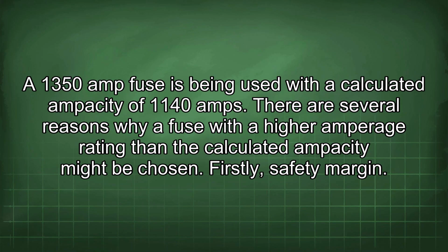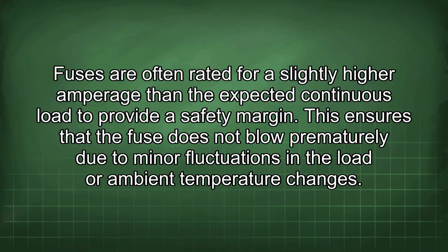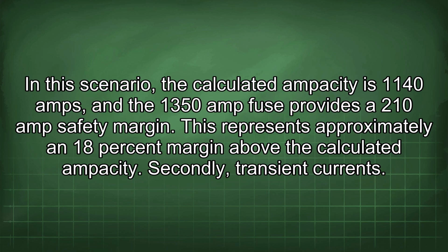A 1350 amp fuse is being used with a calculated ampacity of 1140 amps. There are several reasons why a fuse with a higher amperage rating than the calculated ampacity might be chosen. Firstly, safety margin. Fuses are often rated for a slightly higher amperage than the expected continuous load to provide a safety margin. This ensures that the fuse does not blow prematurely due to minor fluctuations in the load or ambient temperature changes. In this scenario, the calculated ampacity is 1140 amps, and the 1350 amp fuse provides a 210 amp safety margin. This represents approximately an 18% margin above the calculated ampacity.